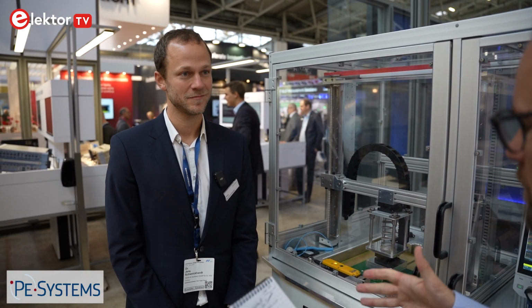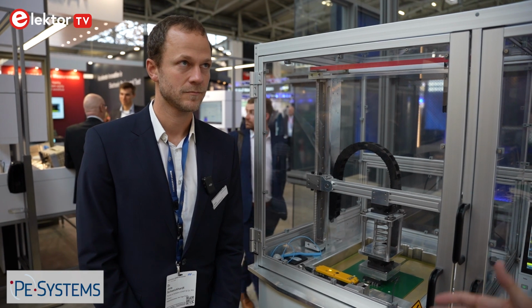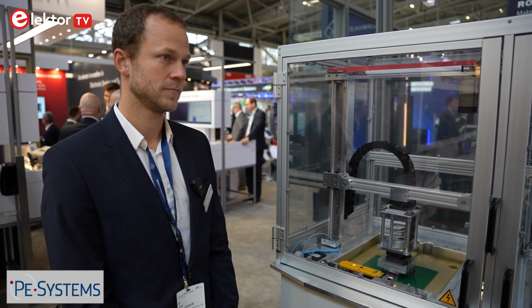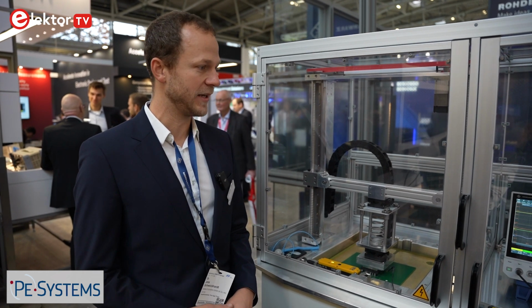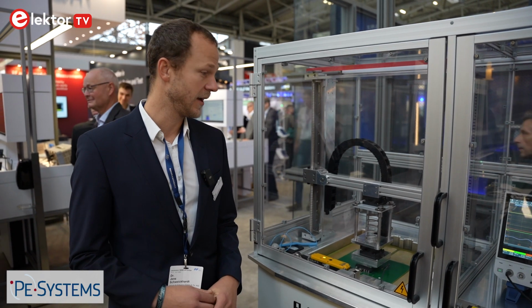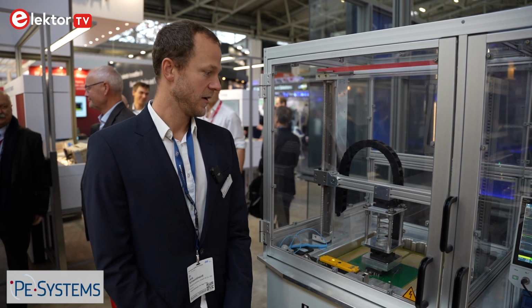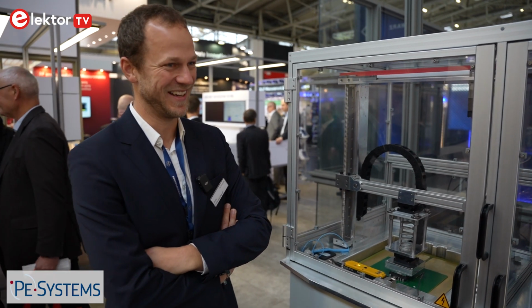And obviously we're transitioning at the minute from silicon devices to wide bandgap. What are the challenges with the double pulse test and the response of wide bandgap devices that we didn't see with silicon? I think the major issue is that we have to consider many high frequency effects, and the biggest challenge is to measure the current with high bandwidth but without disturbing the setup too much. And here there are many ideas, but the perfect solution is not there yet, I would say.